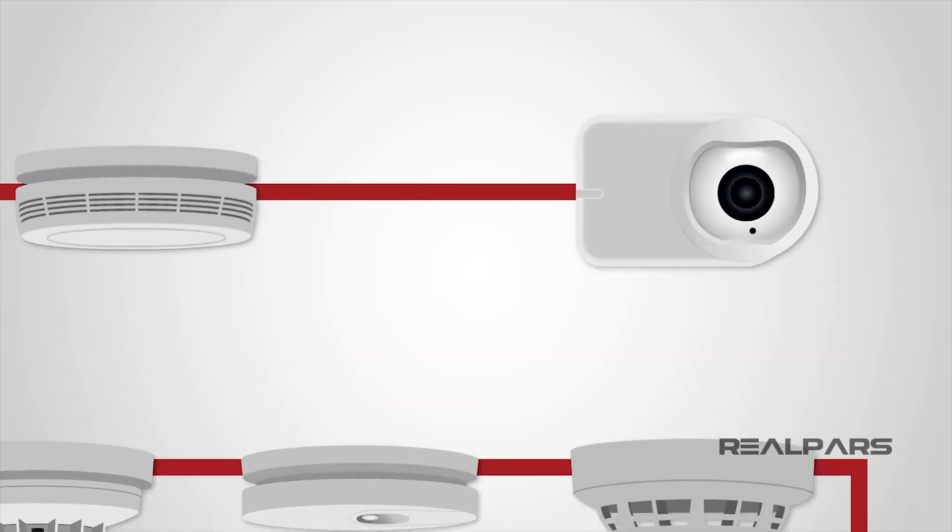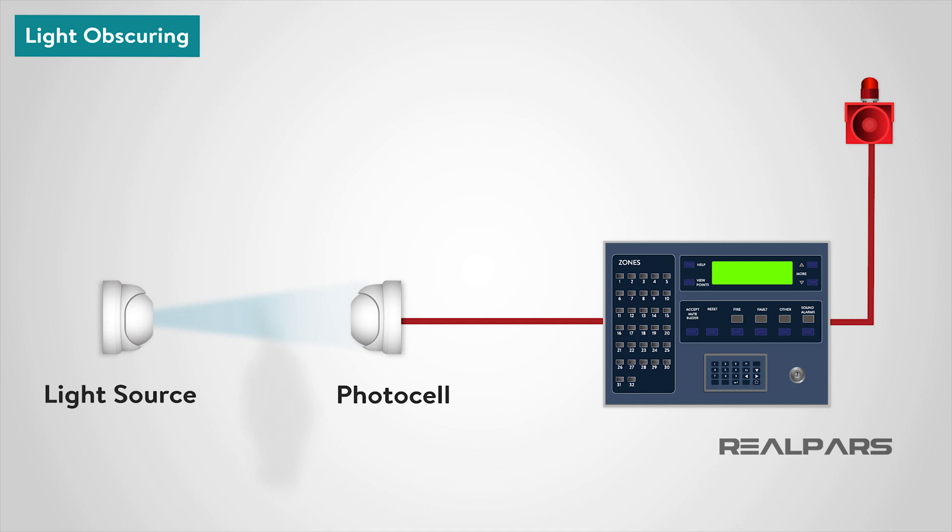In the light obscuring smoke detector, smoke interferes with a light beam between a light source and photocell. The photocell measures the amount of light it receives. The variation in photocell output is being used to initiate an alarm. This type of detection can be used to protect large areas with a light source and photocell positioned some distance apart.